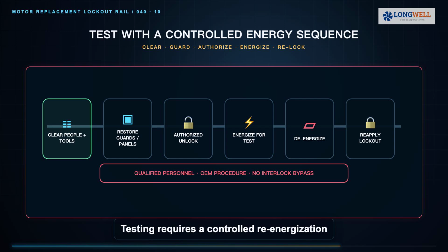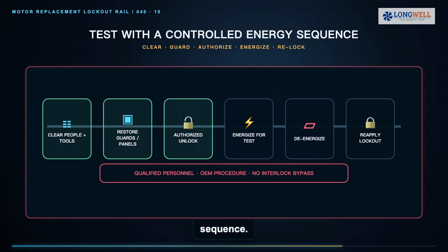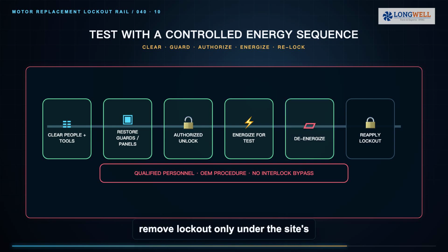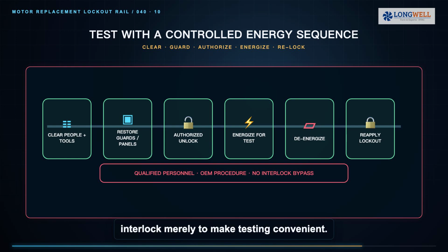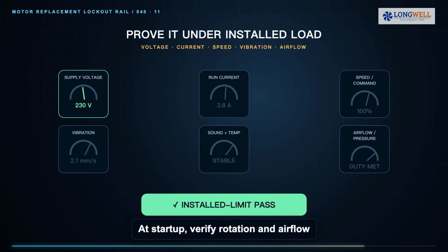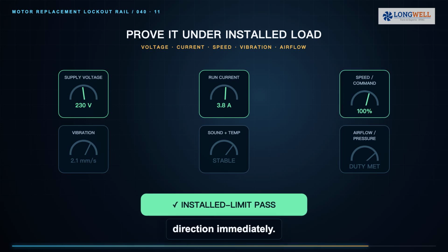Testing requires a controlled re-energization sequence. Clear people and tools, restore guards and panels, remove lockout only under the site's authorized procedure, and energize for the required test. If further adjustment is needed, de-energize and reapply lockout before reopening the equipment. Never defeat a door switch or safety interlock merely to make testing convenient. At startup, verify rotation and airflow direction immediately.